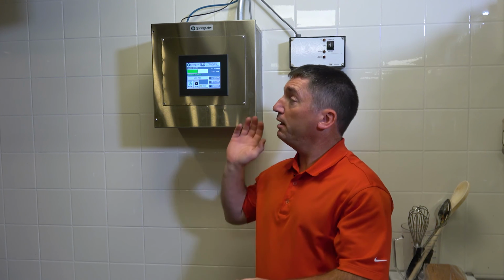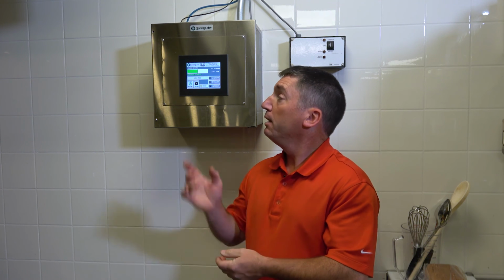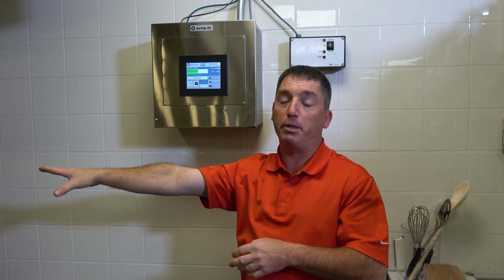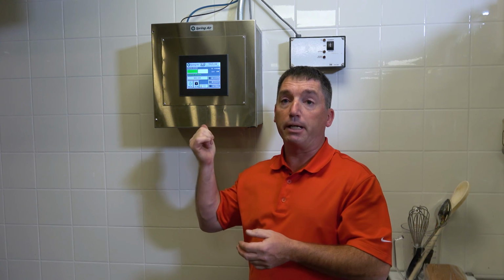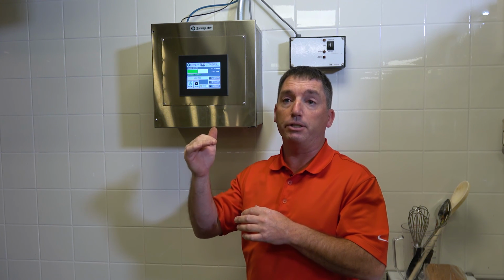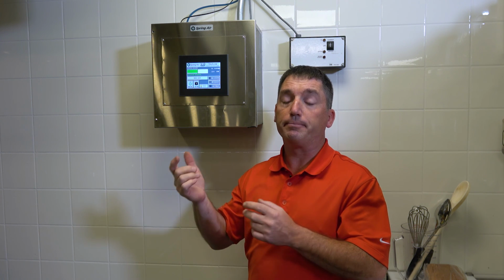Okay, we're now in the kitchen, and behind me here is the Spring Air, what we call the TrueFlow controller. This is an on-demand ventilation system controller. The way it functions is the exhaust hood here that's above the appliances has temperature probes in the exhaust collar, and as the cooking load increases, obviously our exhaust air temperature is going to get warmer. The system is going to recognize that and automatically increase the amount of air that's being exhausted, and at the same time increase the amount of air that's being brought back in to replace that.